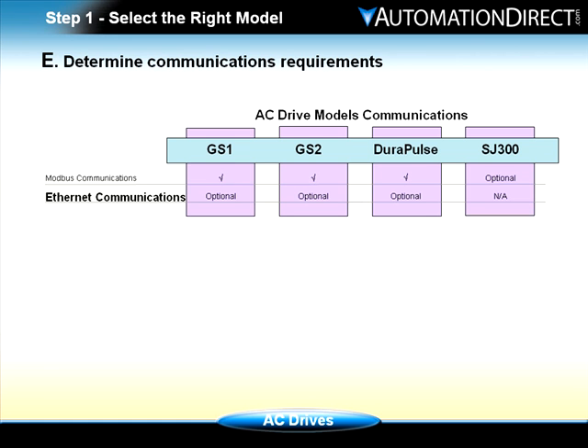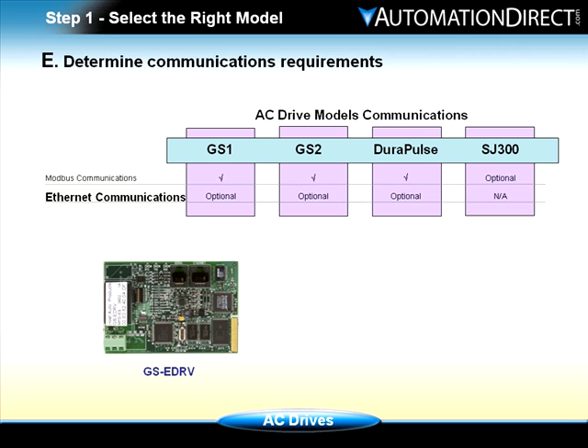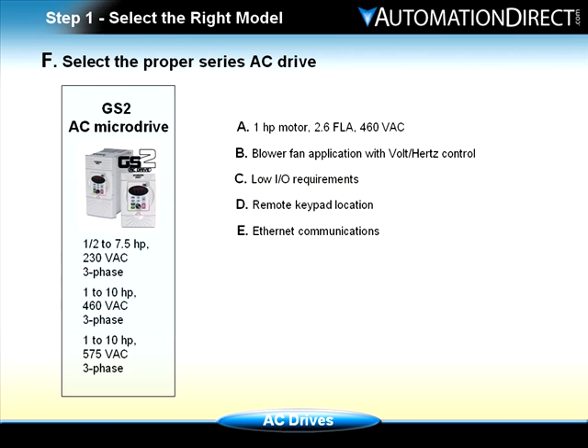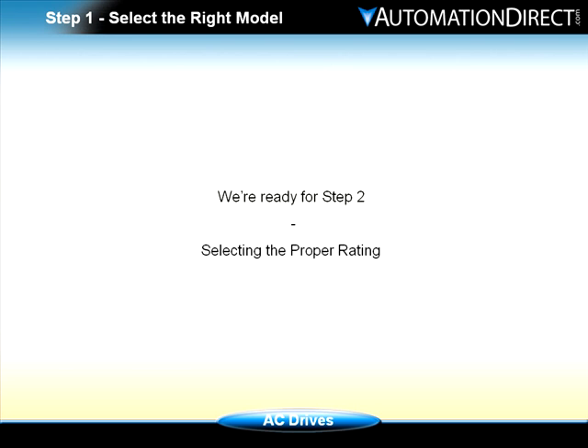The GS1, GS2, and DuraPulse AC drives also have the capability to communicate through an optional Ethernet interface by utilizing the GS-EDRV interface board. This board receives the Ethernet connection from the master and sends out an RS-485 serial Modbus communication to the AC drive. We'll be using Ethernet to communicate with the PLC. Based on all the facts, we have determined that the most cost-effective AC drive series that fits our application is the GS2 AC micro drive. We're now ready for Step 2, selecting the proper rating.